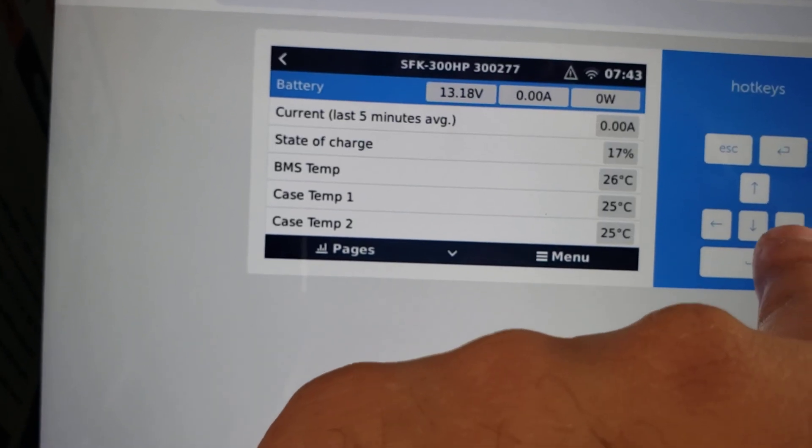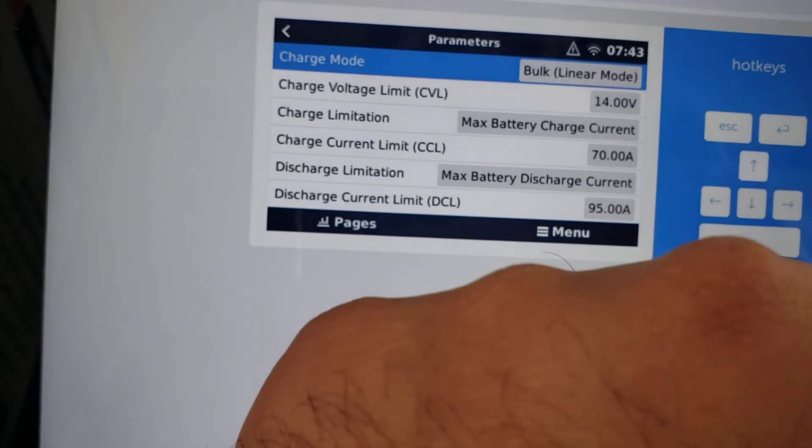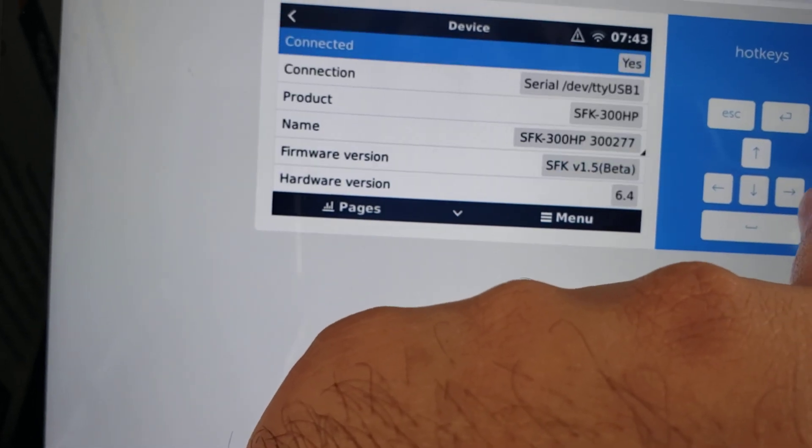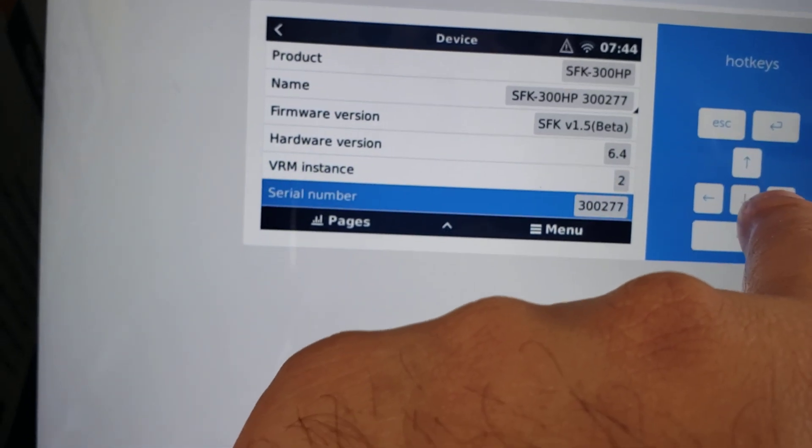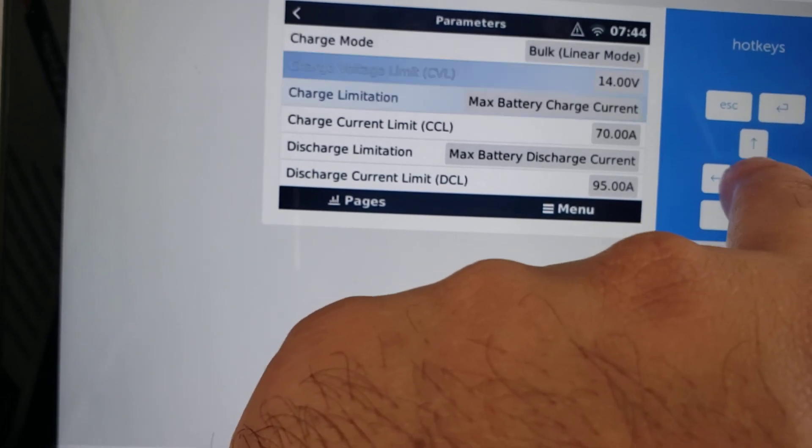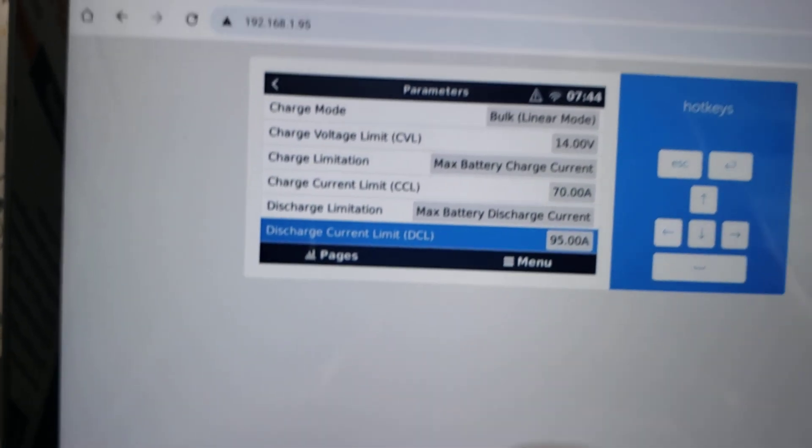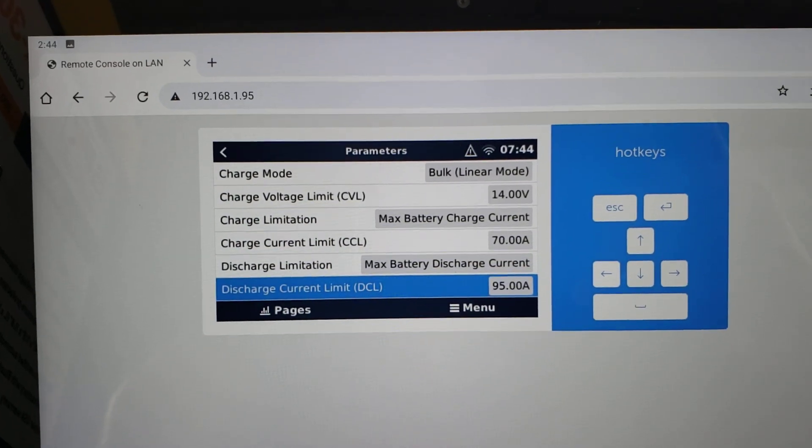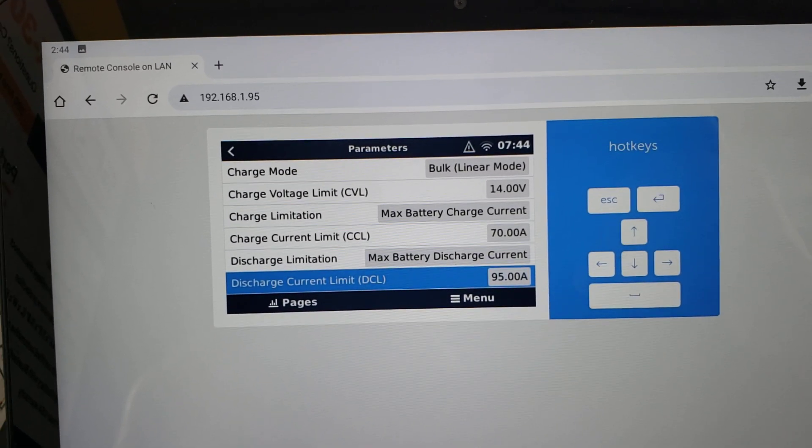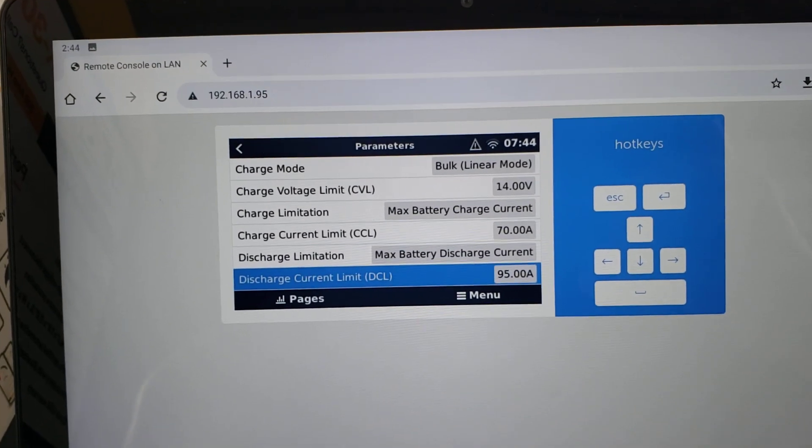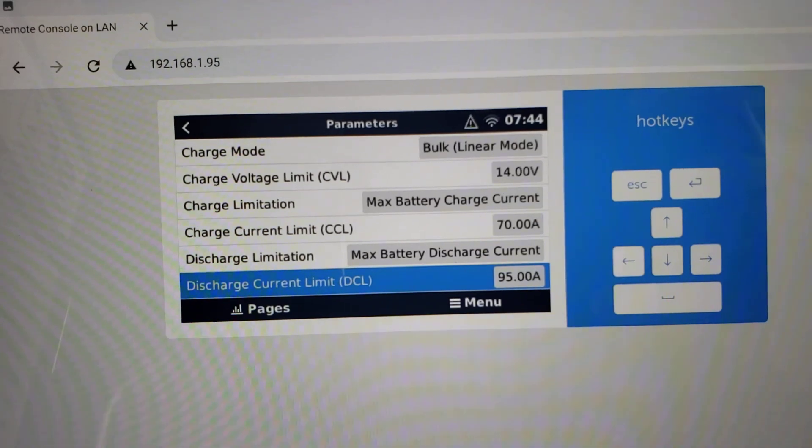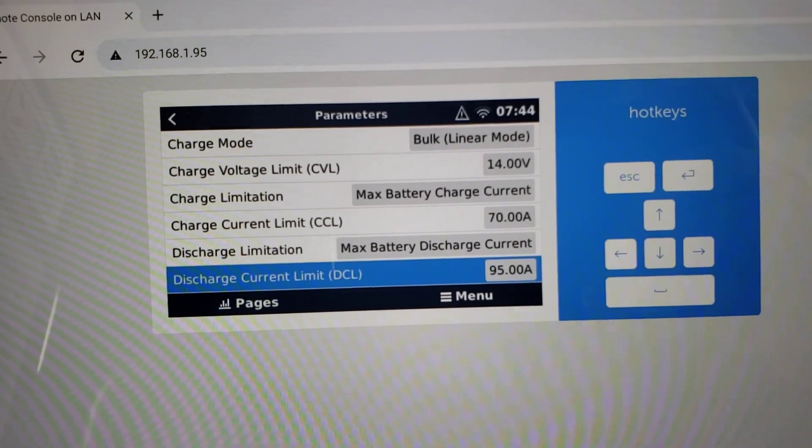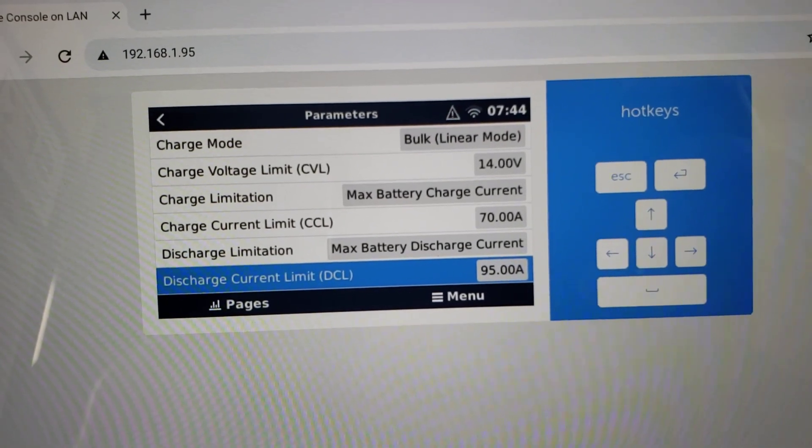Okay, and we go to parameters. Sorry, we go to device. These have, you know, that's version 1.5 beta, but we have our serial numbers here. And I think in our parameters we have charge limit 70, discharge limit 95. Now that's just something we put in there. You can't, in a new version we'll let you change it, but what it does is the virtual battery will combine everything. So if you've got three, your charge is 70 plus 70 plus 70, so you have 210 amps that you can charge it. And if you discharge it, you've got 95, well you just combine all three of those, so you end up with like 285 amps that you can charge it as.